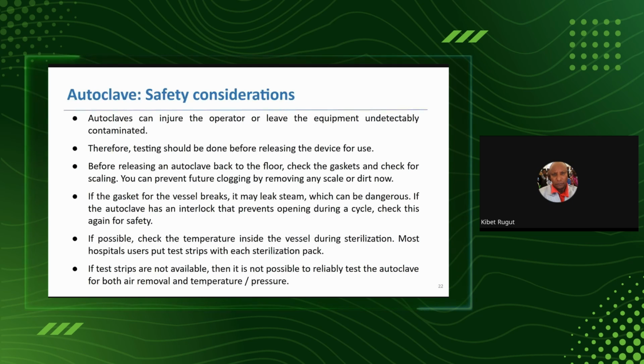Now, safety is a very huge area again in autoclaves, and it can cause injury to the operators. So it is good to follow the instructions carefully, and in some situations it demands wearing PPE. Sometimes you have autoclaves that you are not required to operate without hand gloves or without eye goggles. Some of these situations I've seen in some places. Some people have also built an into-the-wall autoclave, so that the operator side is not exposed to the hazards that could occur if there is a problem in the main autoclave.